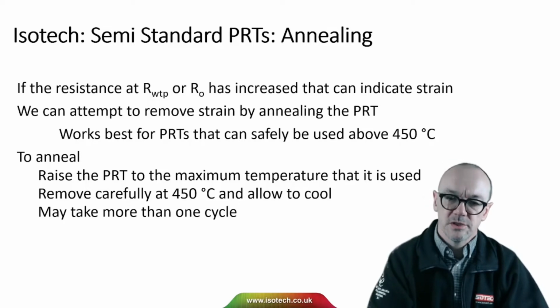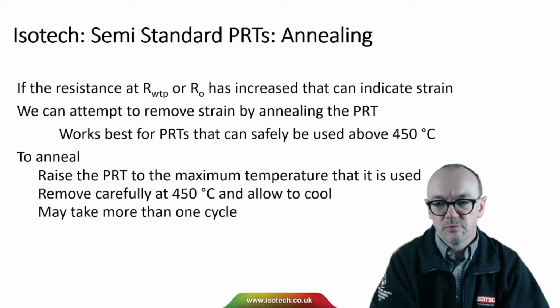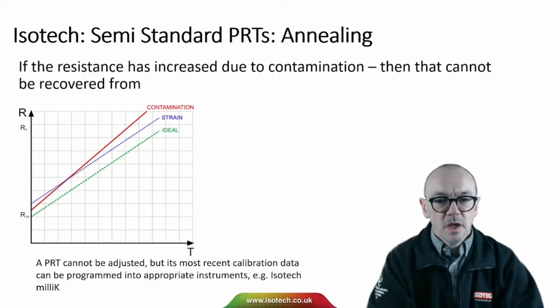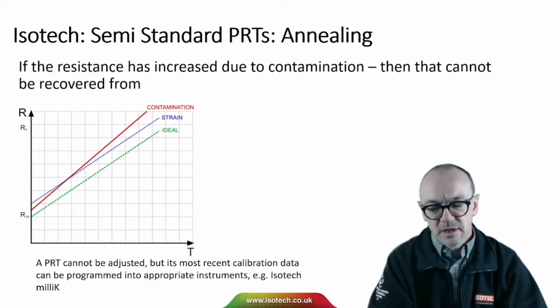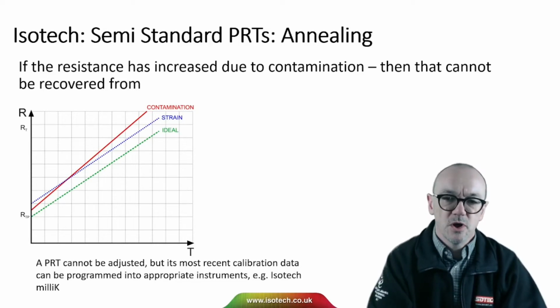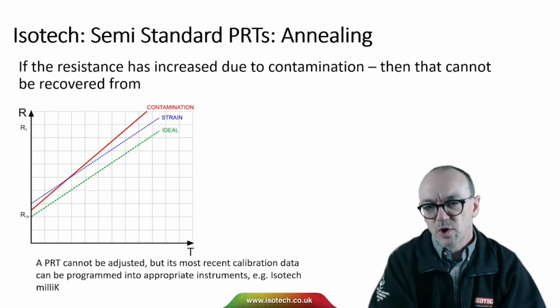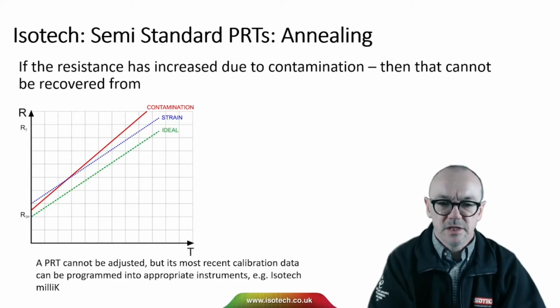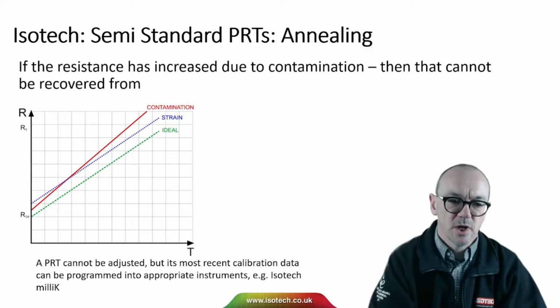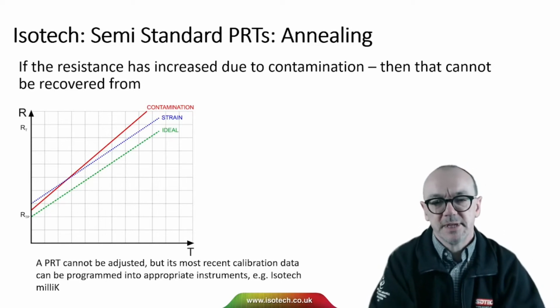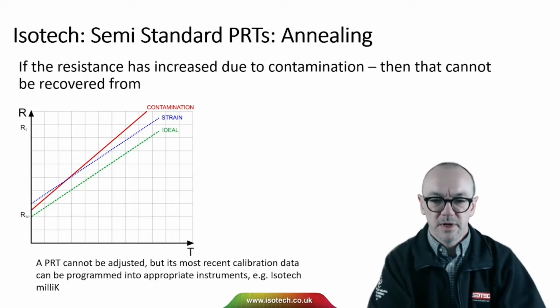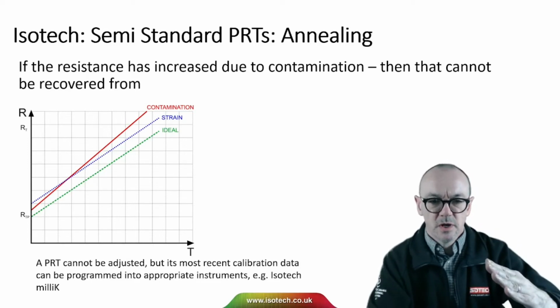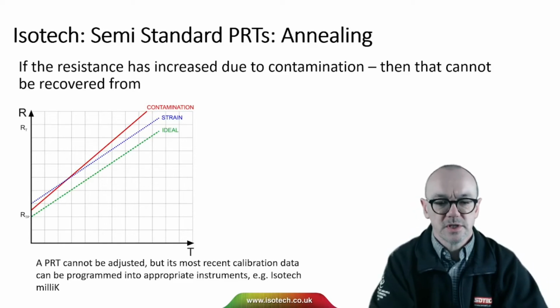And then if we re-measure the resistance at the water triple point, if we see that value come down, then we're getting confidence we are reducing the strain. And it may take more than one cycle to fully anneal a thermometer. If the resistance has increased due to contamination, then that cannot be recovered from. There's no technique to recover a contaminated thermometer. With a contaminated thermometer, you can see strange things in the resistance to temperature curve. Maybe it drops and rises, it can be unpredictable. But with strain, you typically see a linear offset across the whole of the range. So we can anneal to remove strain, but not contamination.